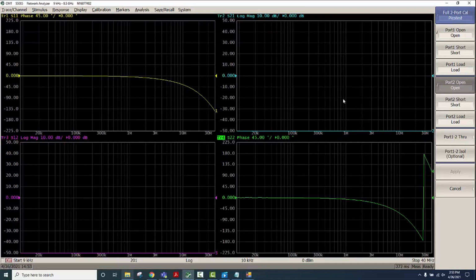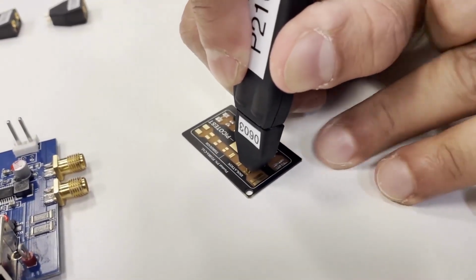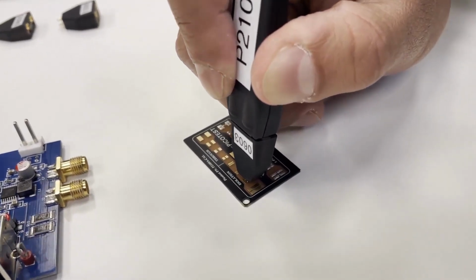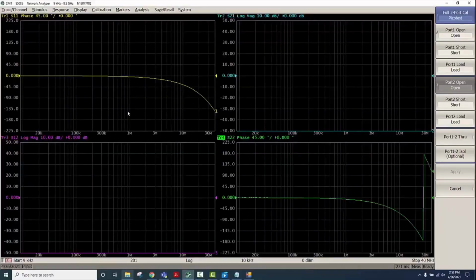So you can see S11 and S22 phase is close to 0 there at low frequencies. So next, what we'll do is the isolation. So this is to perform isolation as well as the short calibration. So now looking at this at the VNA screen, we have S11 and S22 close to 180 degrees, so indicating a short connection. So we'll click on short, port 1, port 2, as well as we'll do the isolation.